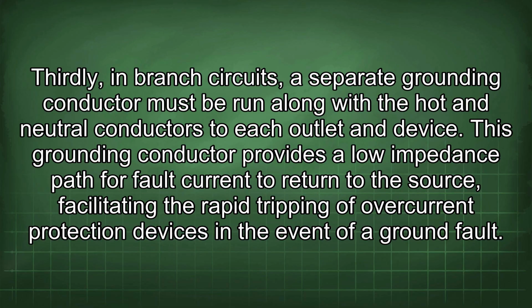Thirdly, in branch circuits, a separate grounding conductor must be run along with the hot and neutral conductors to each outlet and device. This grounding conductor provides a low impedance path for fault current to return to the source, facilitating the rapid tripping of overcurrent protection devices in the event of a ground fault.